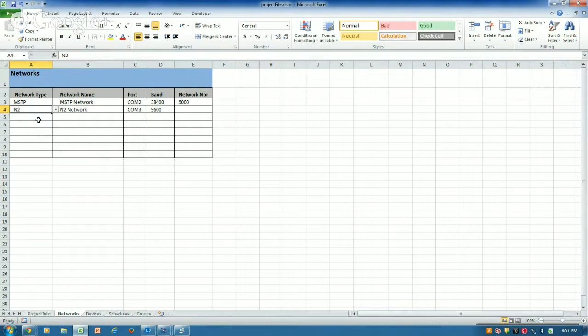You're also allowed to add multiple BACnet ports, or let's say an N2 port here to support legacy N2 networks. It automatically increments the port number and puts the right baud rate in there, and in N2 world, network numbers didn't mean a whole lot, so I'll just put in 1 there. So now I've created a station with a name and some networks.